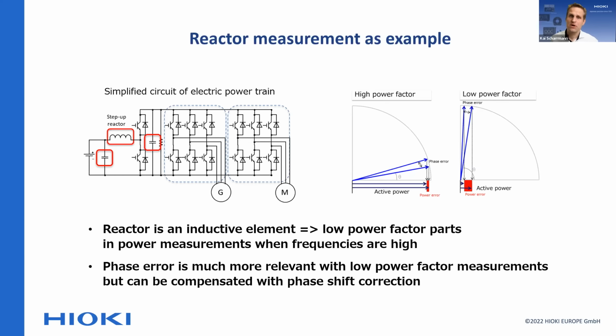And that's actually especially why for these kind of SiC and GaN measurements, why for this kind of step-up reactor measurements, all these kind of things, it's so important to have this phase shift correction function and to have suitable sensors that are also capable of dealing with the frequencies that you're looking at. Because of course, you're not only looking at the base switching frequency, you do look at harmonics as well in your measurement.